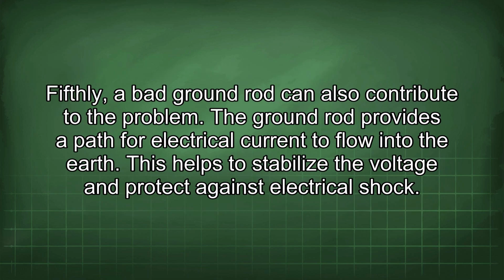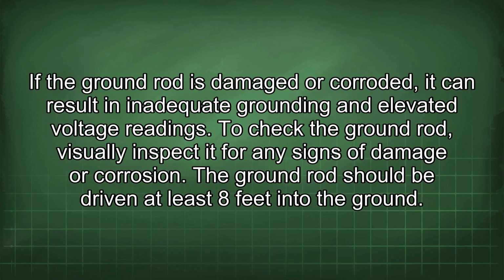Fifthly, a bad ground rod can also contribute to the problem. The ground rod provides a path for electrical current to flow into the earth. This helps to stabilize the voltage and protect against electrical shock. If the ground rod is damaged or corroded, it can result in inadequate grounding and elevated voltage readings. To check the ground rod, visually inspect it for any signs of damage or corrosion.